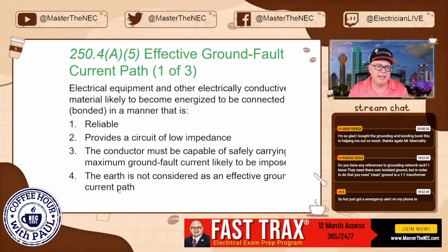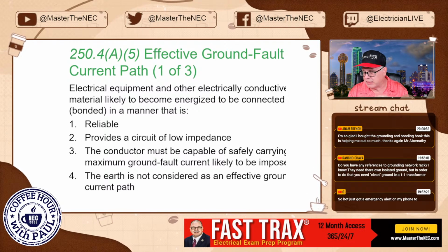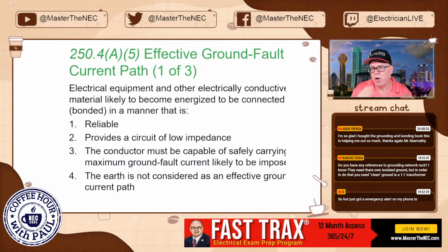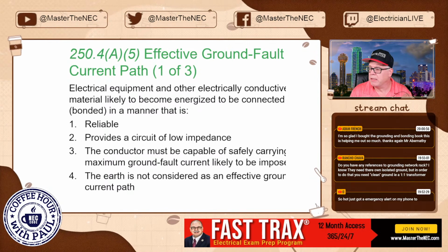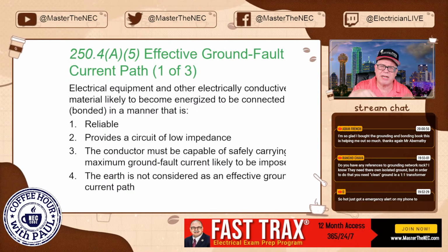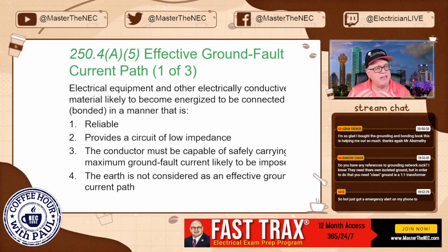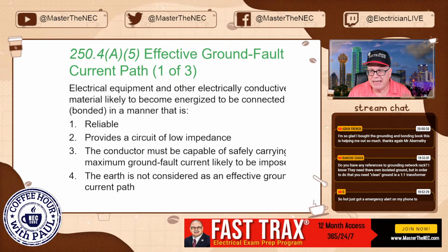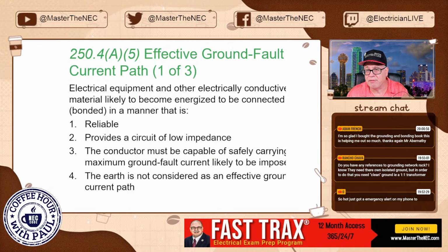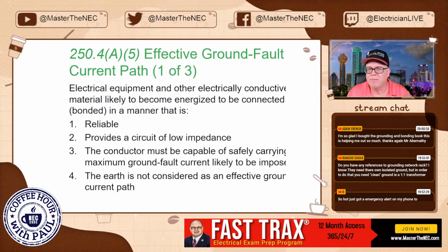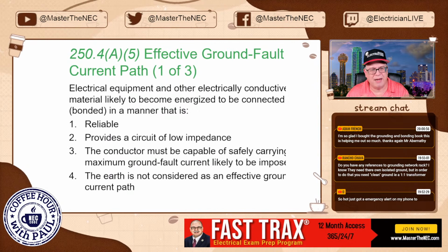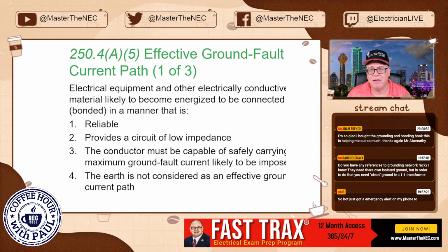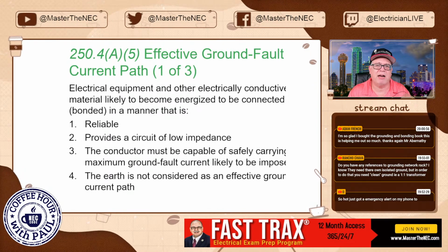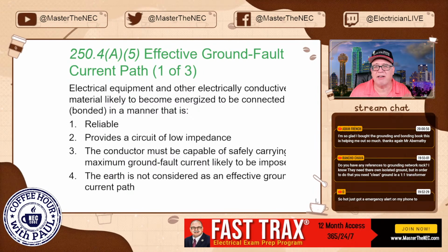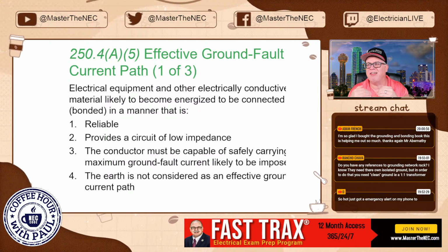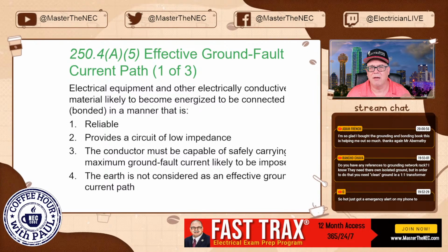I just got somebody the other day post something right before I ditched TikTok. We were talking about post lights in a parking garage and a parking lot. And he swore that you didn't need an equipment ground there because driving a ground rod would be effective. And I said, that is impossible. He says, oh, I've seen it happen. I'm like, it's not going to happen. If you don't have an equipment grounded conductor run and you simply take it and drive it in the earth, the resistance is just too high.